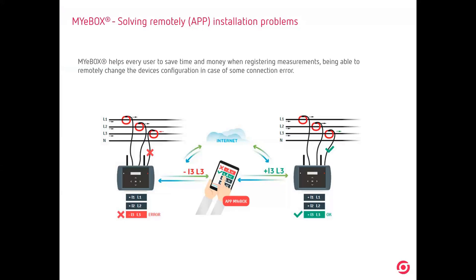So if you go to the installation with a typical analyzer and you make this mistake, you leave the analyzer 1 week and you come again after 1 week for uninstalling and downloading the data, you will see that you do not have correct data. You have to measure again, but you have to make the trip. Imagine, I see people from Philippines here in the webinar. I remember when I stayed with them in Philippines. We took 3 hours to do 30, 40 kilometers, okay? 3 hours, so you have to take 3 hours for going, 3 hours for coming back to the office, waiting 1 week, again the same, 3 hours and 3 hours, and you have made a mistake, you have to do it again. So you will be losing time by the vehicle, by engineering people, you have to take a plane, for example, whatever. You will be having cost, you have to sum different costs that are indirect costs for us, okay? That will increase the measurements.